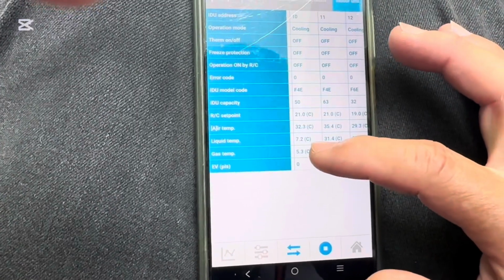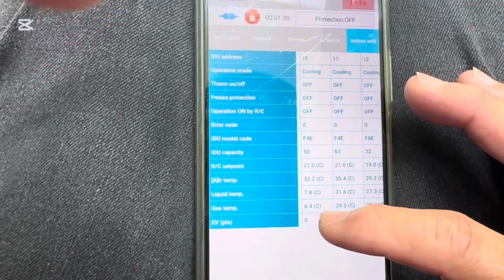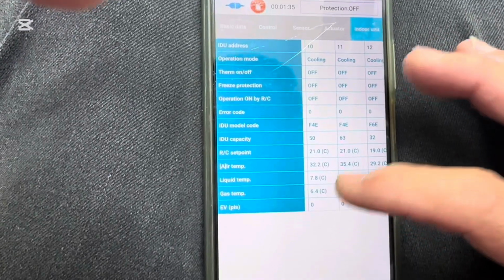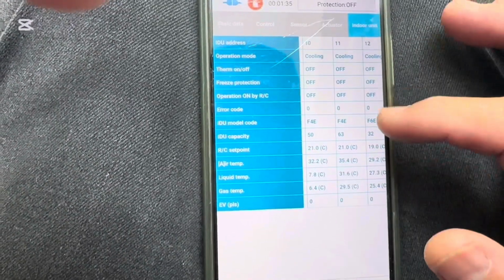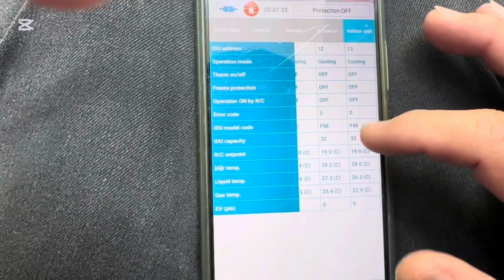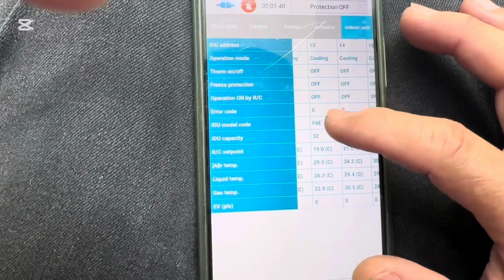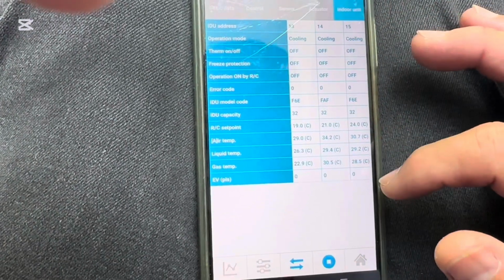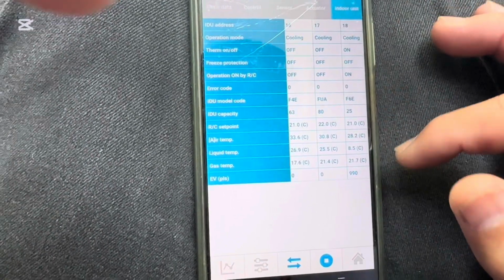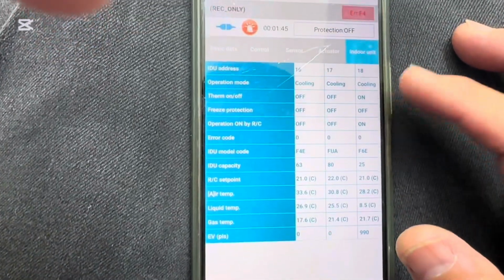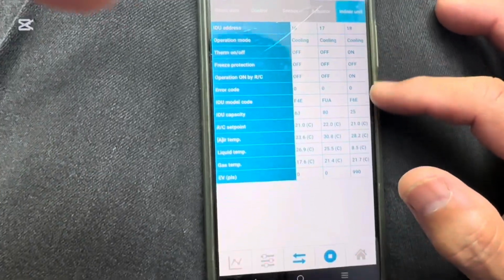But the liquid pipe temperature and gas pipe temperature are the lowest. That means this valve, we need to check what's the problem. The LEV valve. Okay. 13, 14, 15. Okay. 16, 17, 18. Yeah, just now we only switched on one unit.